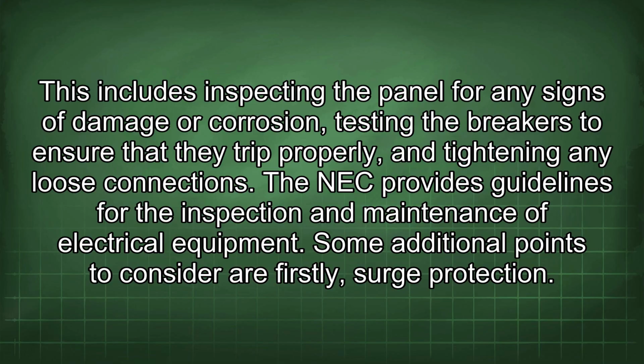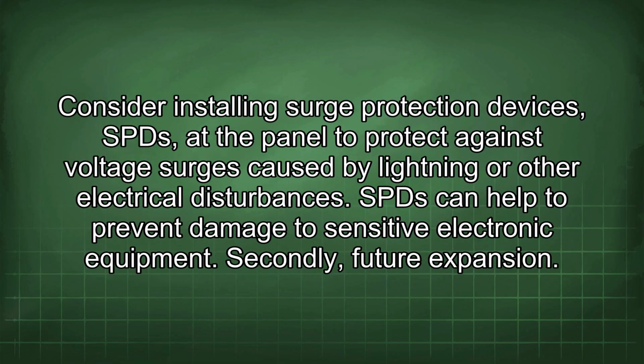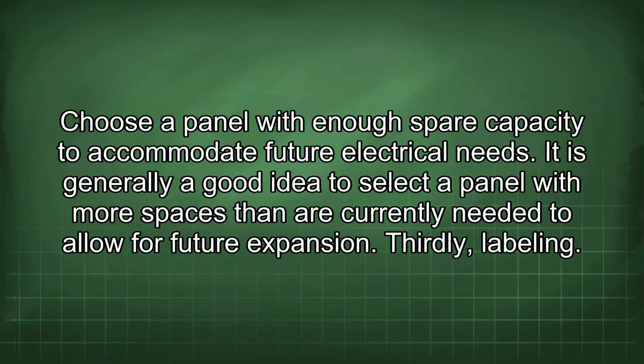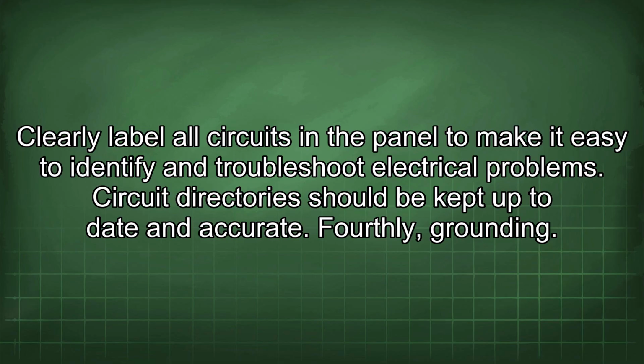Some additional points to consider are, firstly, surge protection. Consider installing surge protection devices, SPDs, at the panel to protect against voltage surges caused by lightning or other electrical disturbances. SPDs can help to prevent damage to sensitive electronic equipment. Secondly, future expansion. Choose a panel with enough spare capacity to accommodate future electrical needs. It is generally a good idea to select a panel with more spaces than are currently needed to allow for future expansion. Thirdly, labeling. Clearly label all circuits in the panel to make it easy to identify and troubleshoot electrical problems.